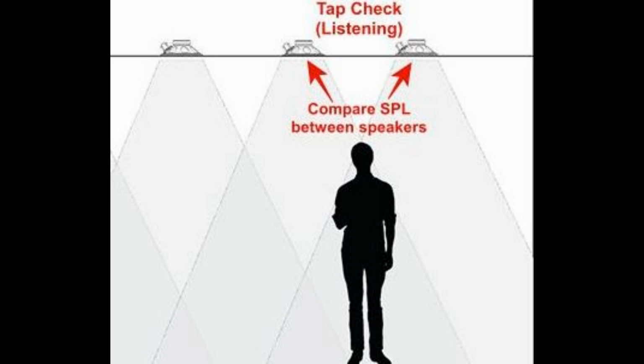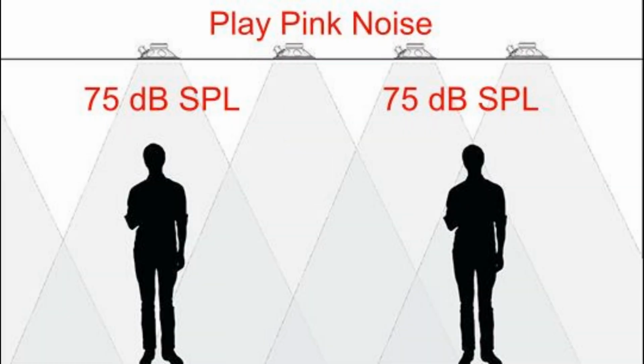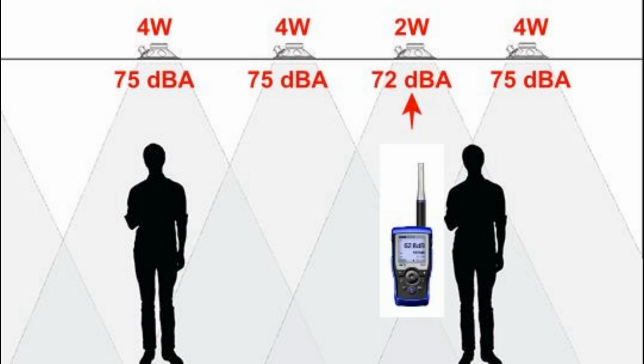While walking in the speaker zone, listen for sound pressure level differences between speakers to verify they are tapped at the same value. Noticing the level differences can be tricky, and it may be necessary to play back pink noise instead of music. With pink noise you can walk the zone using the NTI XL2 sound pressure level meter. If a speaker is noticeably different compared to the rest, then most likely the tap value was set incorrectly.